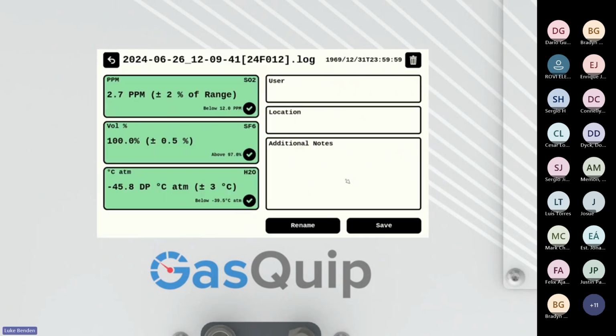All right, so here is the results screen for running a test. Obviously, we have our SO2, SF6, and H2O like we talked about earlier. It's the same setup that we had mentioned with the units, the accuracy of the sensor itself, and then that user set test limit that we talked about earlier. So all of our tests passed on what we had set for the threshold. So anything above 97% for this, anything below -39, and below meaning drier as you go lower in dew point. So all of these passed.